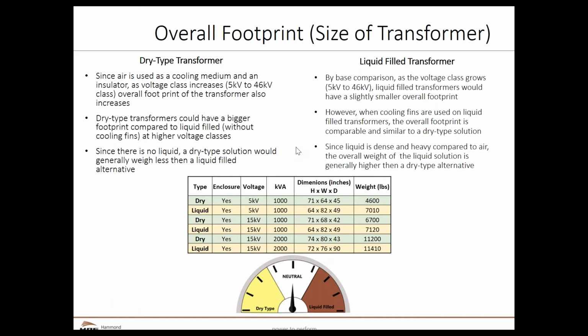So again, when we look at the footprint of liquid versus dry, we include the cooling fins, we do see some advantages with liquid filled. Typically, it's a little more apparent in the larger sizes. Smaller, you might actually see some advantages. I'm sorry, in the larger sizes, you might see some advantages in the dry type. In the smaller sizes, you might see some advantages in the liquid filled.